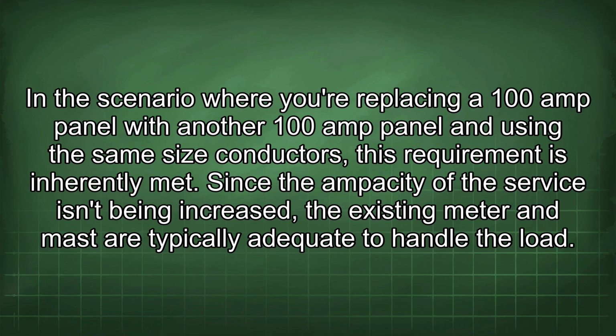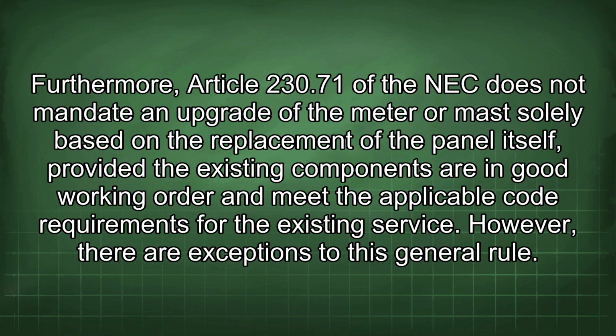Since the ampacity of the service isn't being increased, the existing meter and mast are typically adequate to handle the load. Furthermore, Article 230.71 of the NEC does not mandate an upgrade of the meter or mast solely based on the replacement of the panel itself, provided the existing components are in good working order and meet the applicable code requirements for the existing service.